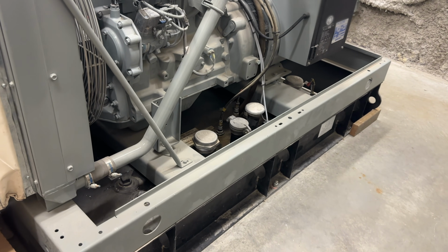This generator here runs on diesel. This has to run on diesel because this school and many of our other schools with generators are designed to be a community shelter. They are built to the higher earthquake codes and standards, more like a hospital or fire hall, those type of structures would be, because they need to be, unlike many other buildings where they may survive the earthquake, but they can't legally be occupied after that event. This building, because it's an emergency shelter, has to be still occupiable after such an event. Therefore, the generator needs to run on diesel because natural gas lines will shut down in any seismic activity. So that's why this is a diesel generator with the tank underneath it.